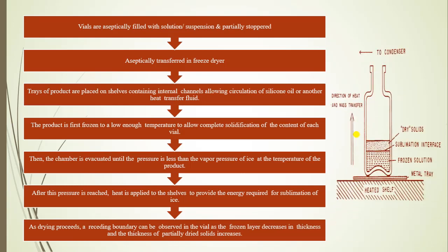Starting with the process overview for lyophilization: as with sterile manufacturing, terminal sterilization does not take place here. Vials are separately depyrogenated or sterilized, and the solution is aseptically filtered. The filtered solution or suspension is filled into depyrogenated or sterilized vials and partially stoppered using special closures called lyophilization stoppers or slotted stoppers. Stoppers are partially closed so that during sublimation, the vapor produced can be released from the vial — otherwise it leads to bursting of the vial. The vials are then aseptically transferred into the freeze dryer.